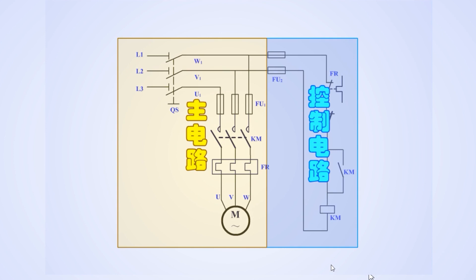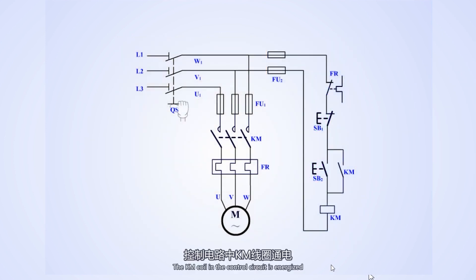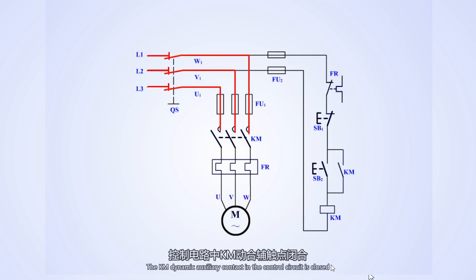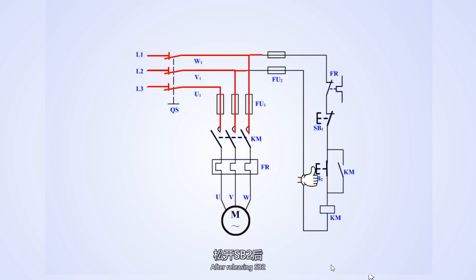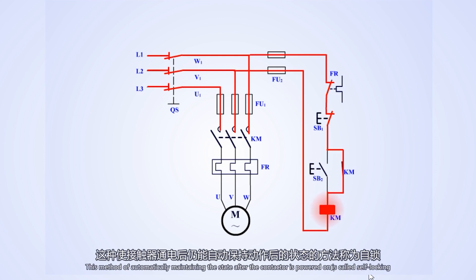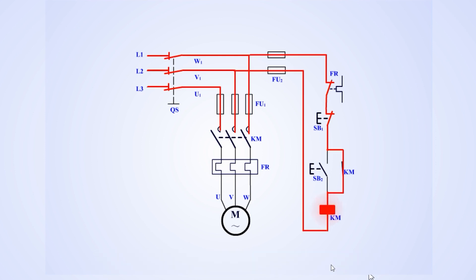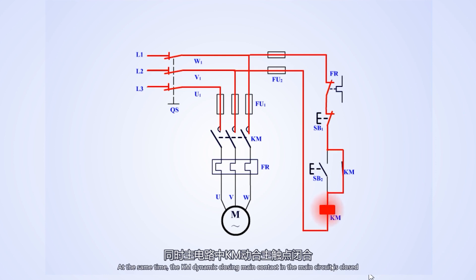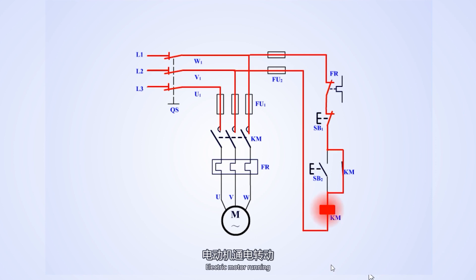Press SB2. The KM coil in the control circuit is energized. The KM dynamic auxiliary contact in the control circuit is closed. After releasing SB2, the KM coil is still energized — this method of automatically maintaining the state after the contactor is powered on is called self-locking. At the same time, the KM dynamic closing main contact in the main circuit is closed, and the electric motor runs.